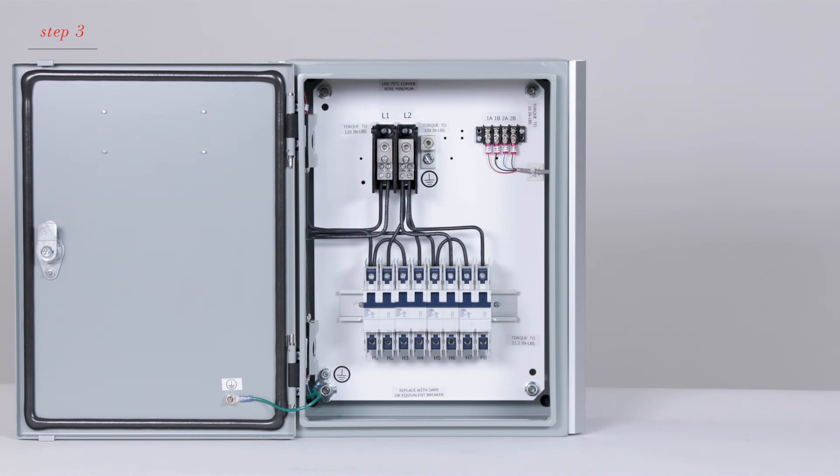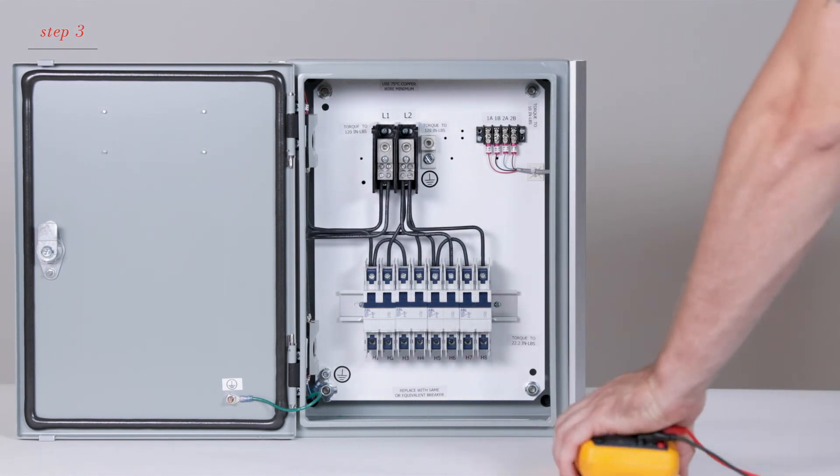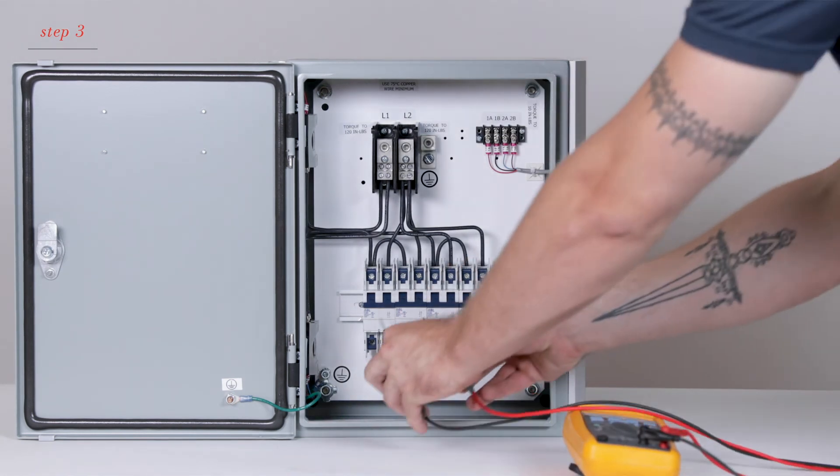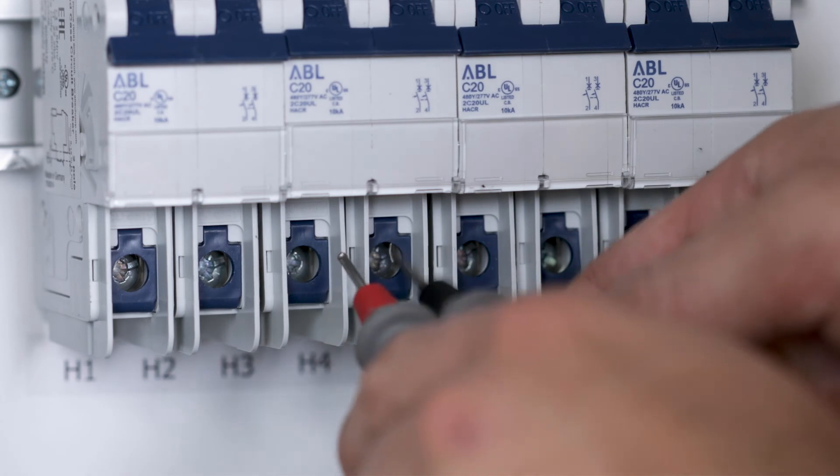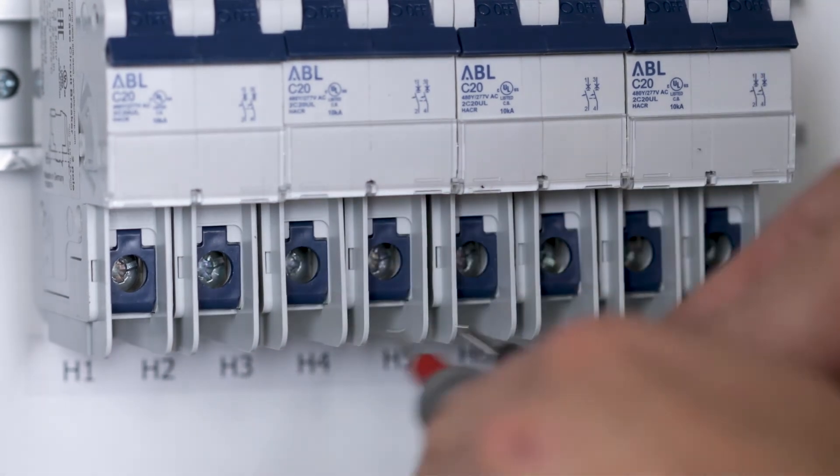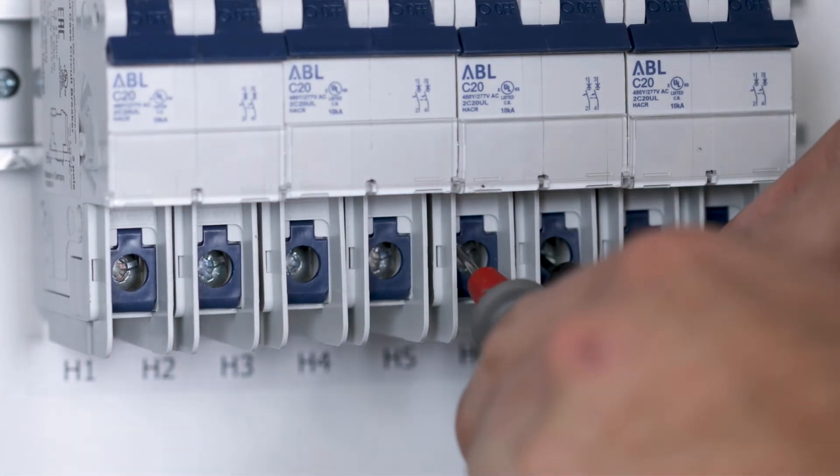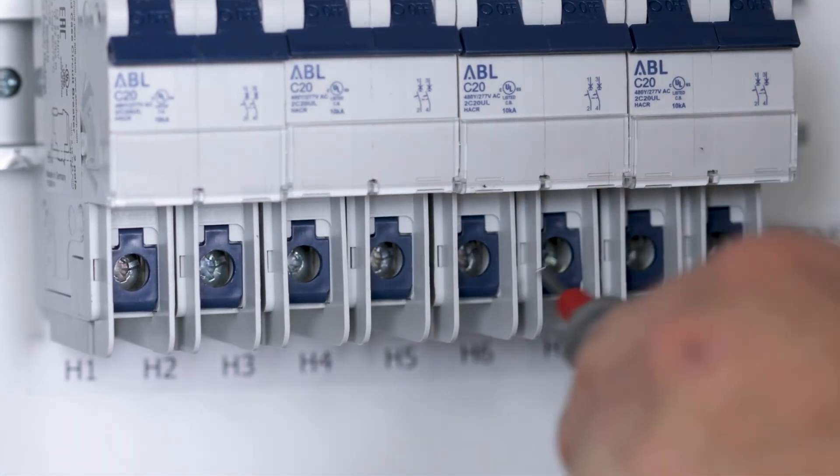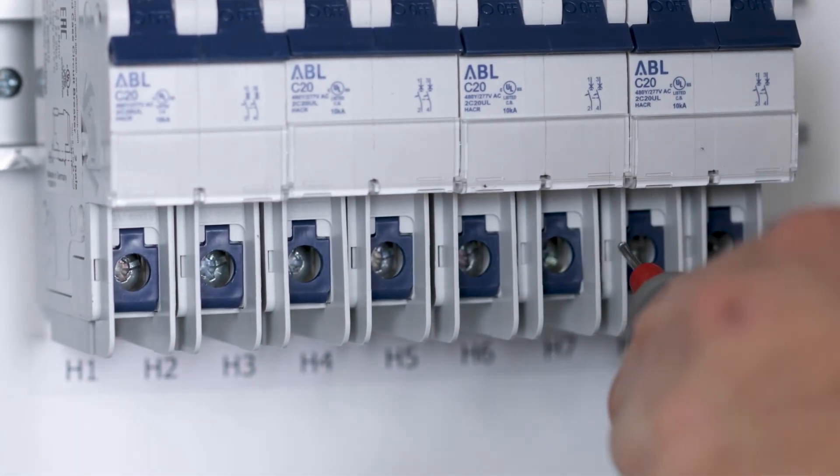Now check to see if there is main feed AC voltage at the output of the breakers. You'll need to take measurements between H1, H2, etc. You'll see this at the bottom of the panel.